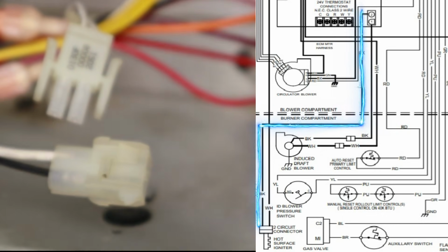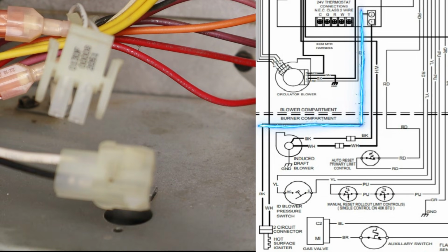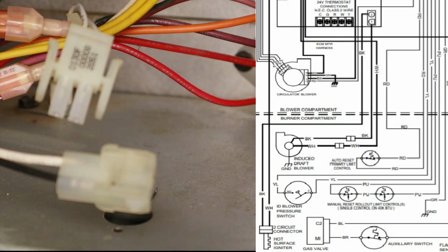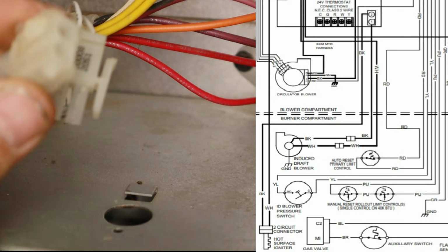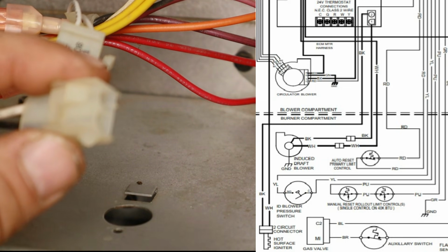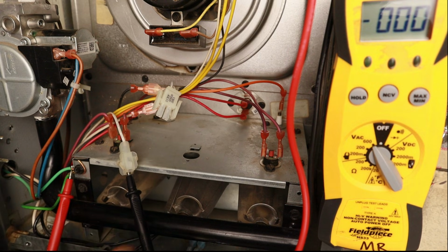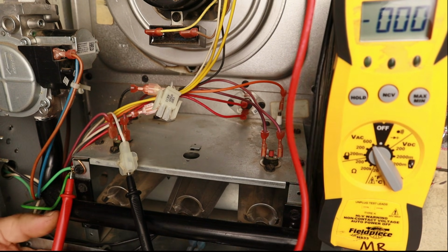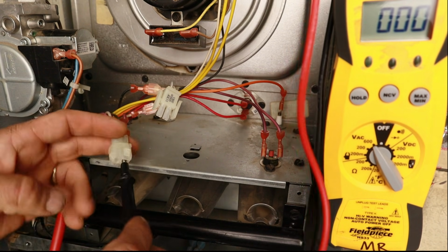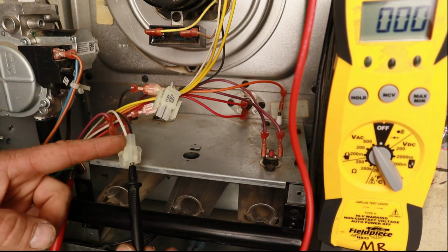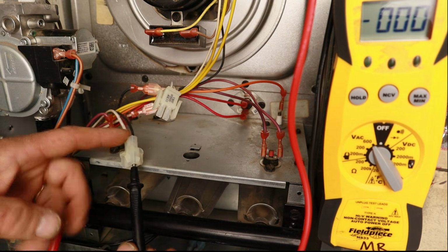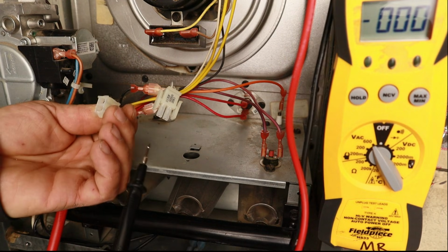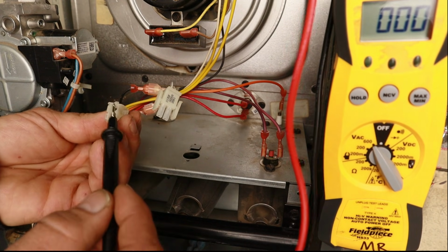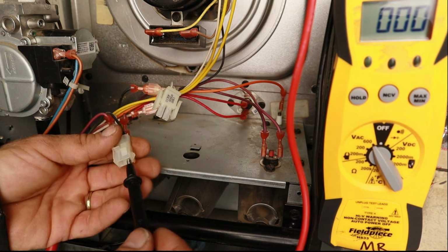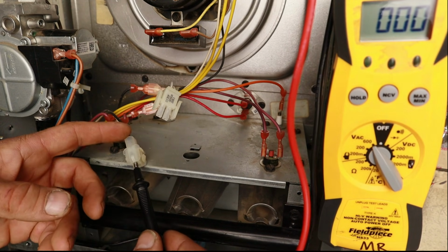So I'm going to leave that unplugged and start the furnace back up again. We're going to have the inducer motor start, the pressure switch is going to be proven, and then we will test for power here going to our surface igniter. So right now I have one probe on ground right here, and I have the other probe going into the black wire that is coming off the control board through that Molex plug. With these Molex plugs, I can use my regular probes because they're not as temperamental as the Molex plugs that go into the control board.